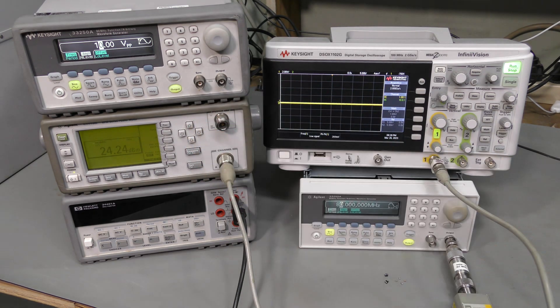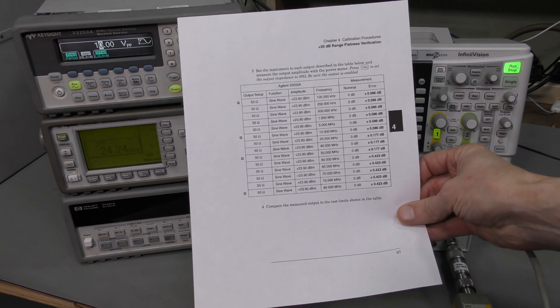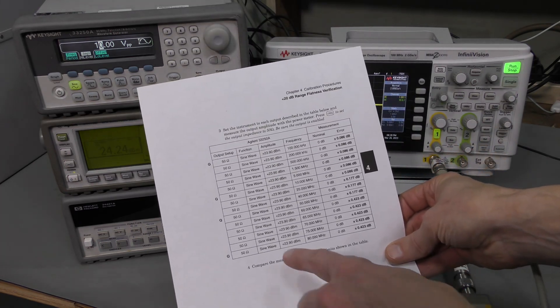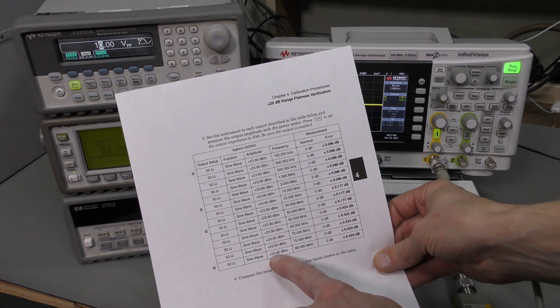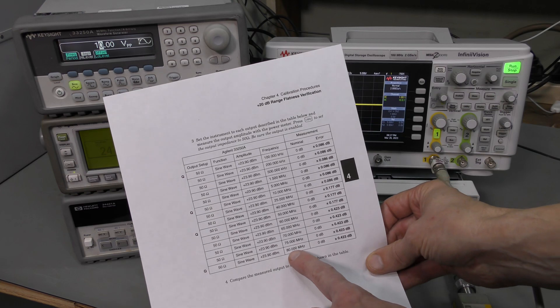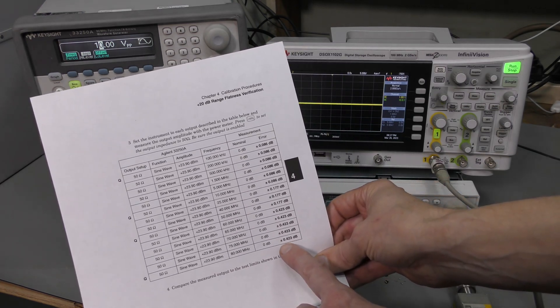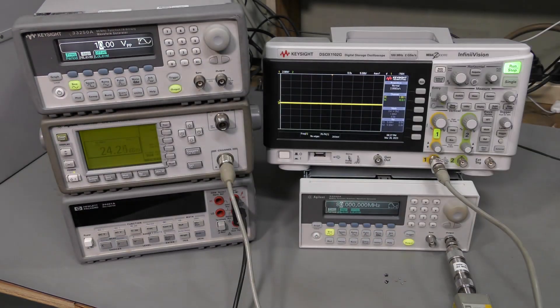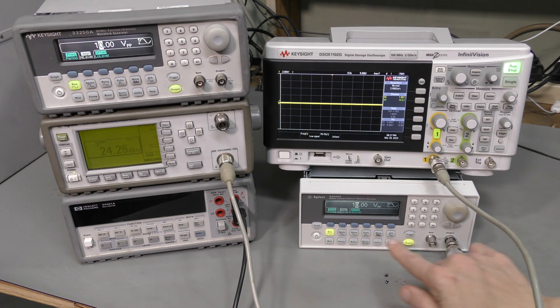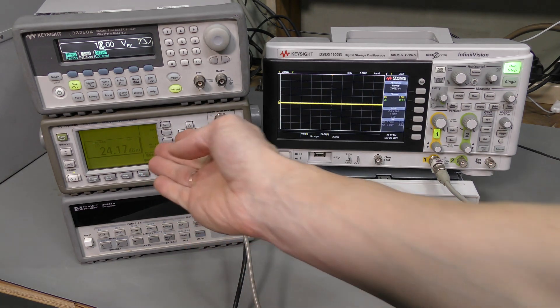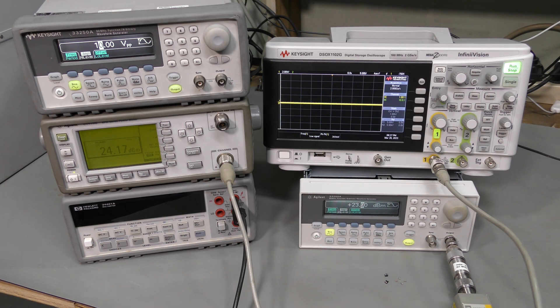So. Here it is. 24.24 dBm. And here I printed from the service manual. Verification table. We are supposed to set 23.9 dBm at 80 MHz and verify that we are within 0.423 dB. So. Let's see. We can set it to 23.9 dBm. And it's a bit higher. 24.17. And it is well within that spec of 0.423 dB.